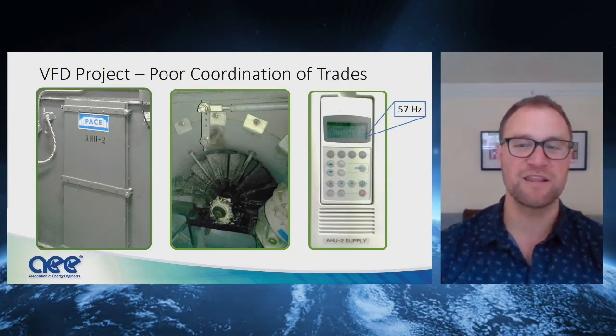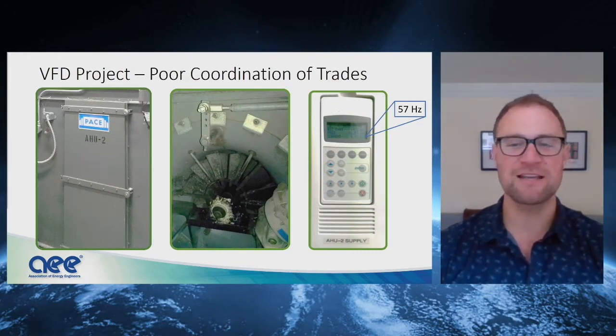And not only were these guide vanes still intact, but they were actively controlling the supply fan. And what you cannot see in this crappy picture on the right is the VFD speed. It's pegged at 57 Hz, so all the work is still being done by the inlet guide vanes, even though this has a VFD. So what the heck is going on here? How does this kind of thing happen?